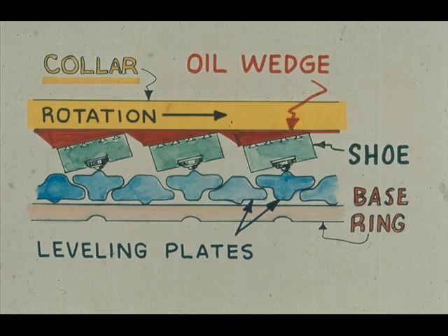A very important part of the oil supply, caused by the relative motion of the collar and the bearing shoes, is wedged in between the bearing shoes and the rotating collar. Hence, in operation there is no metal-to-metal contact of the shoe to the collar.